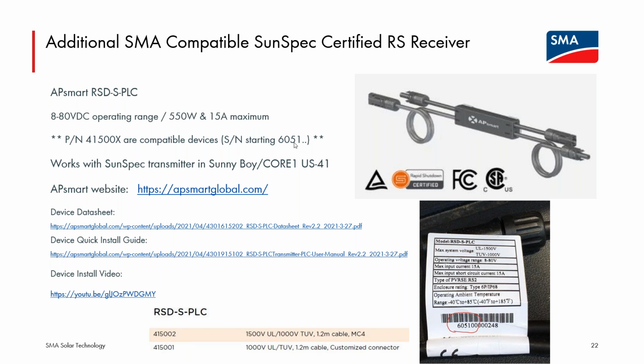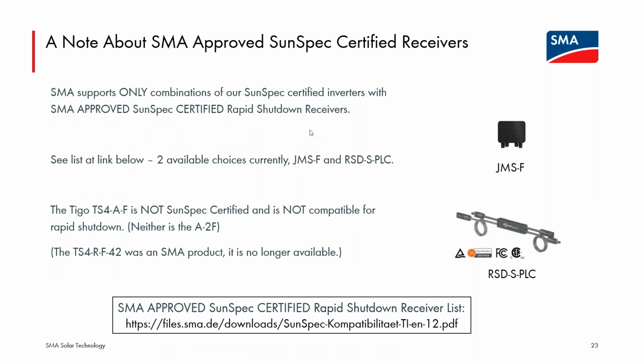That part number, the serial number I have is 6051. That's on the little label here, but for the part number, there are 2 choices that are appropriate. The one that ends in 002 is, I think, their standard product that has true MC4 connectors on both the input and output leads. It is possible to source customized connectors from AP Smart. I'm not certain what sort of lead time that would entail, but if you know you have a ton of modules that may not be MC4 connectors, it's possible to get those customized. But the common off-the-shelf device has MC4 connectors for both input and output, just like the JMS device. So again, either of those 2 devices.